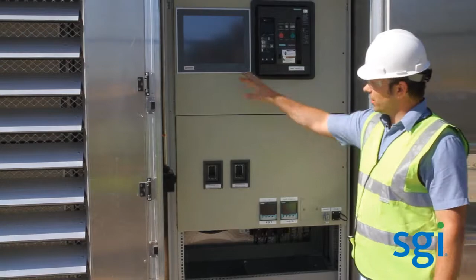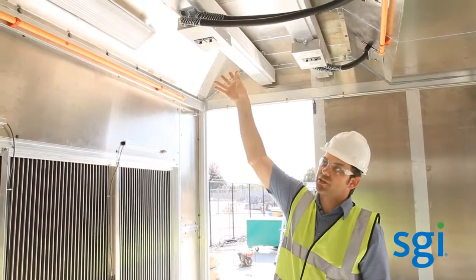So here we are back inside the unit, and when we're talking about electrical, SGI really affords the customer almost limitless choices in the types of power that they can have enter the unit. This particular unit has 2 bus bars, dual bus bars, and in data center terminology, it's in an A and a B fashion. So we actually have 2 sources of power coming into this unit. And as you can see, the bus bar offers the customer what is technically called a bus plug, offers them several different types of configurations and what we call bus drops or cable drops down to PDUs or power strips in a rack.